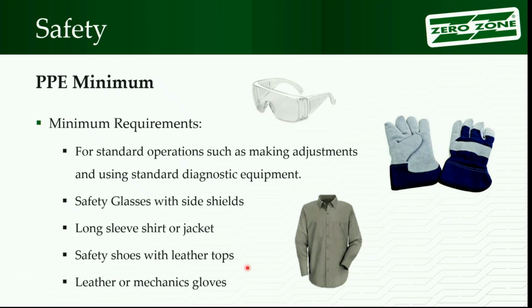So PPE, again, this is stuff you should have in your truck, things you bring along with you, things you ask the boss for. Safety glasses, again, it's cold. You could have cold, could be abrasive. You can have oil. You can actually have just plain old dirt fall off the machine room when you're doing something. So you want to protect yourself from that. Gloves are nice to have. Again, it's cold. And then, of course, on the discharge side, we tend to have higher discharge temperatures than other refrigerants. So you have the other side, and we don't talk about it a lot, but you can burn your hands, burn your arms hitting the discharge line, just like other refrigerants. So that's where you get into long sleeve shirts. Can be better. I know, difficult.